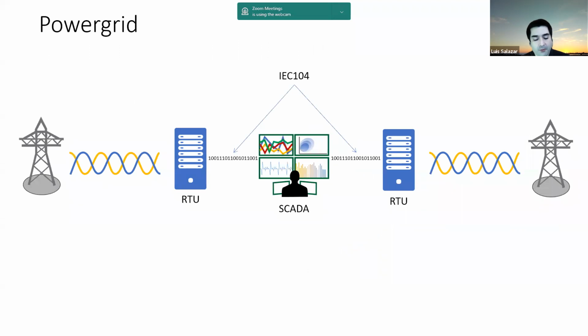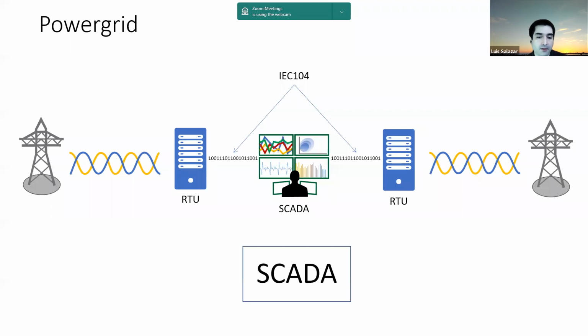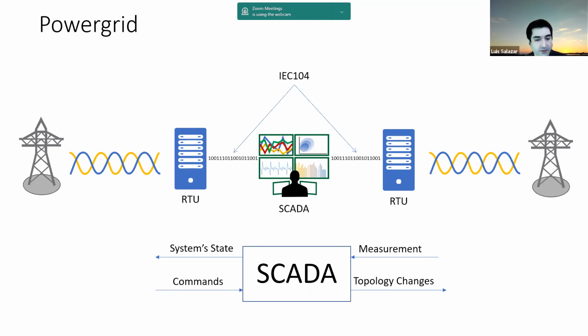And here is where the 104 is important. This is the type of traffic that our research is primarily interested in, the traffic between the SCADA and the RTUs. This is the IEC 104. These are the packets that either contain the information from the substations that are being controlled or the commands that the SCADA is giving to the different RTUs. So the SCADA will take the measurements and give the operator the system state, and the operator will issue commands to the SCADA, and the SCADA will send the topology changes via the IEC 104 to the different RTUs.